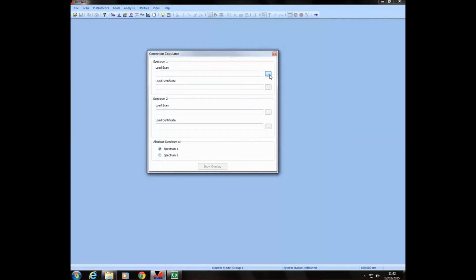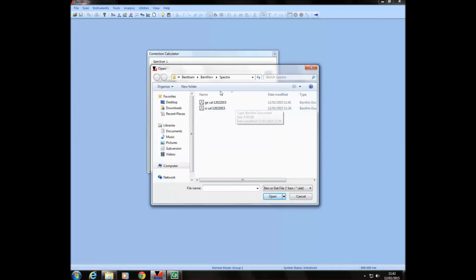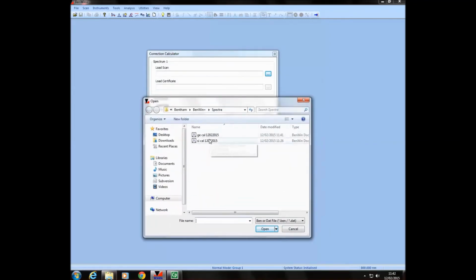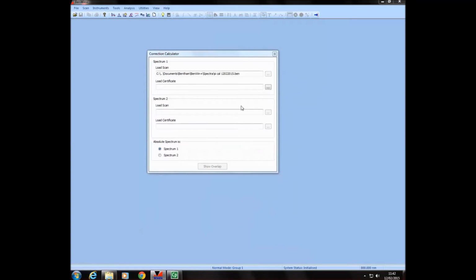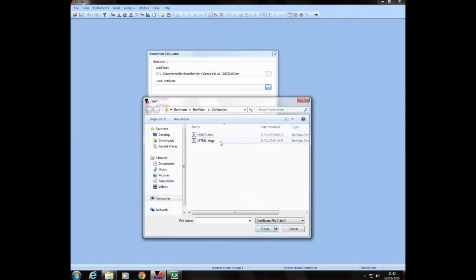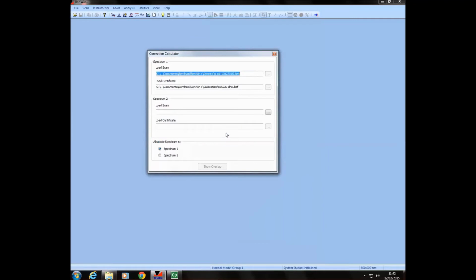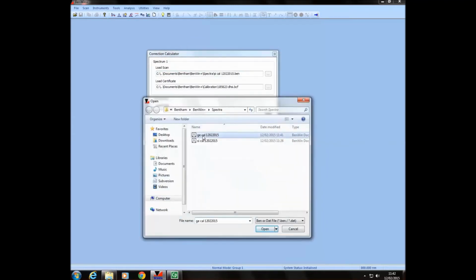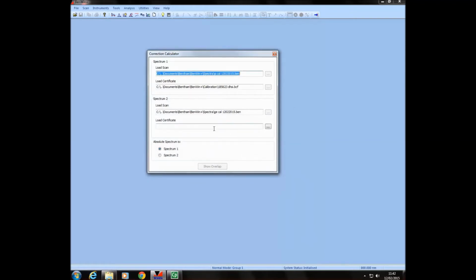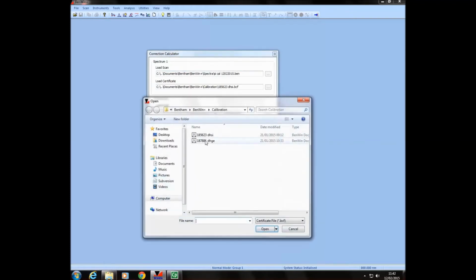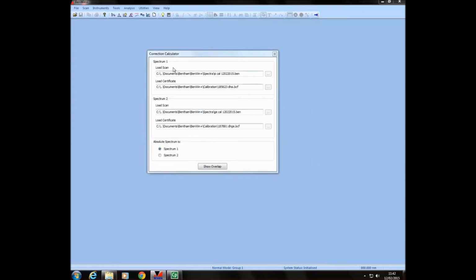Spectrum 1, let's take as the silicon device. The scan is our measurement of the silicon reference diode, and the certificate is the calibrated responsivity of the same device. In Spectrum 2 we shall take as our germanium measurement, and the certificate is the certificate of the same device. We can load the germanium as Spectrum 1, silicon as Spectrum 2, there's no import there. What is important is which absolute spectrum we take.